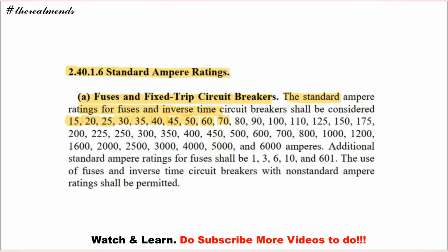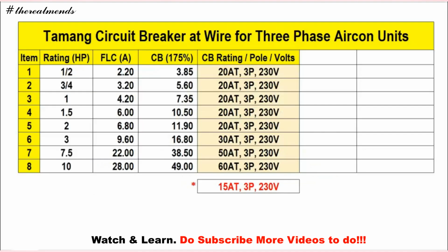So ito yung ating reference to size up ng magiging rating ng ating circuit breaker based on this standard ampere rating. Okay, so from the PEC code, meron na tayong na-arrive na circuit breaker rating, poles at saka volt. So yung ating pole is naka 3 pole siya, 230 volts. So sa ating 1/2 HP, meron tayong 3.85. So ang prefer ko na use is 20 ampere 3 phase 230 volts.